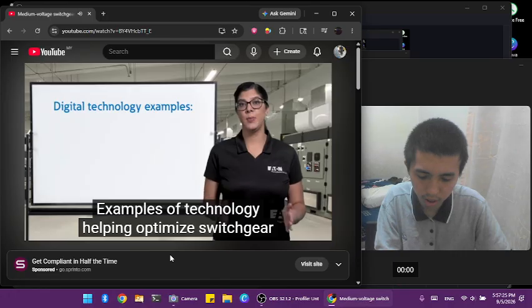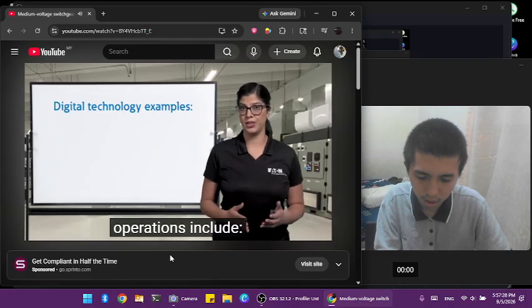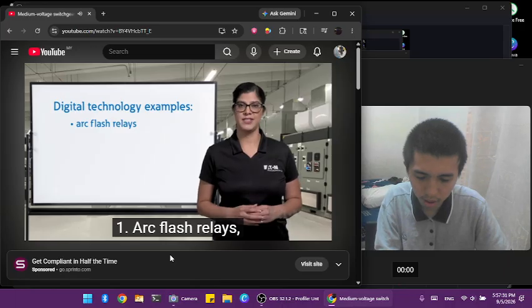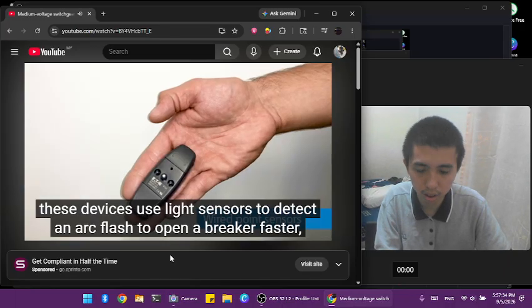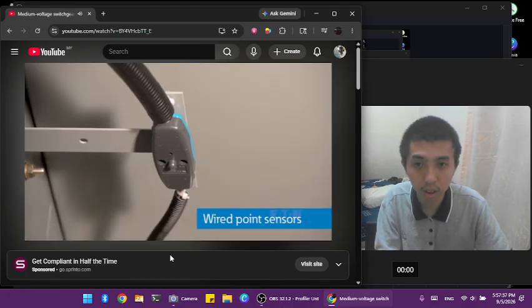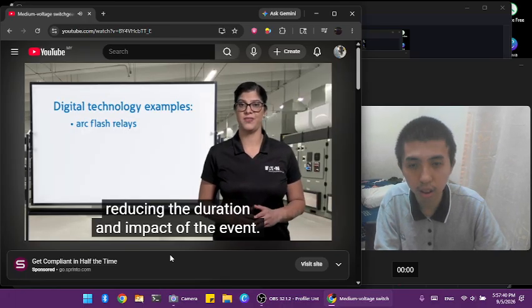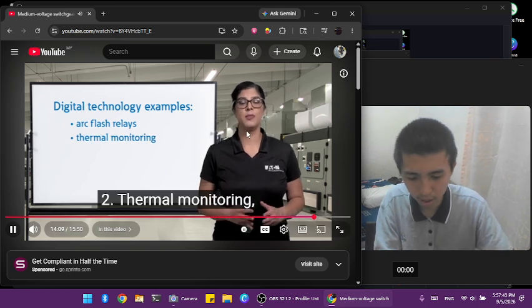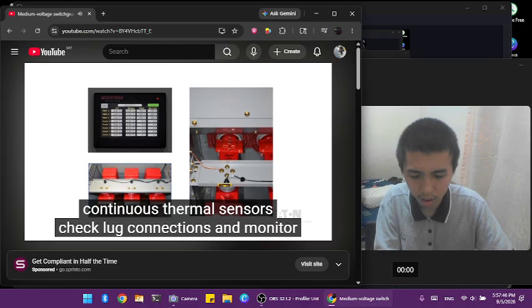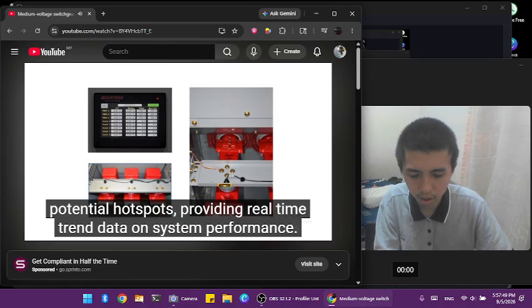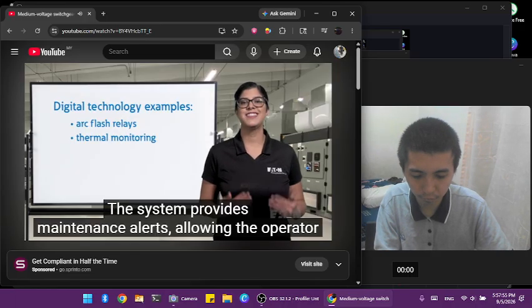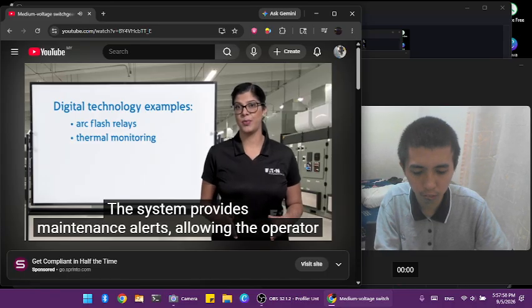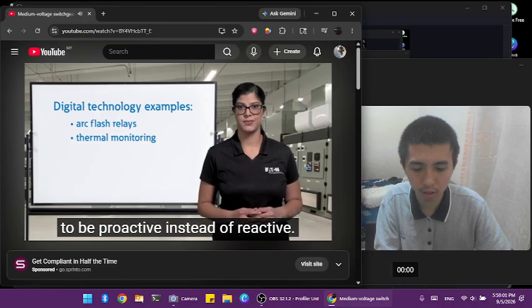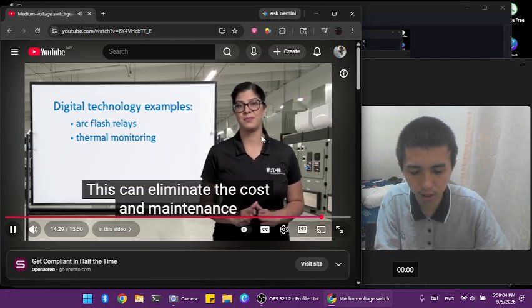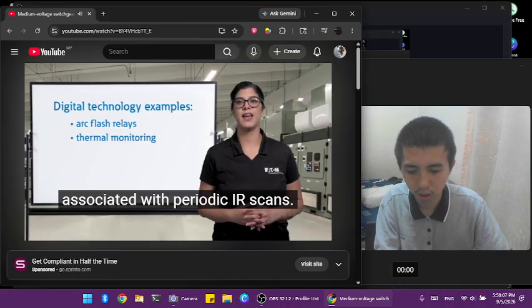Examples of technology helping optimize switchgear operations include: 1. Arc flash relays. These devices use light sensors to detect an arc flash to open a breaker faster, reducing the duration and impact of the event. 2. Thermal monitoring. Continuous thermal sensors check lug connections and monitor potential hotspots, providing real-time trend data on system performance. The system provides maintenance alerts, allowing the operator to be proactive instead of reactive. This can eliminate the costs and maintenance associated with periodic IR scans.